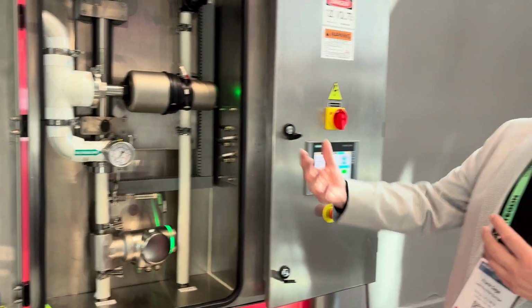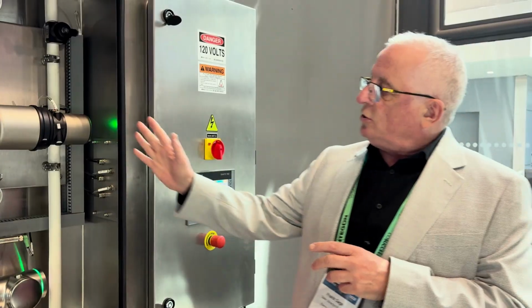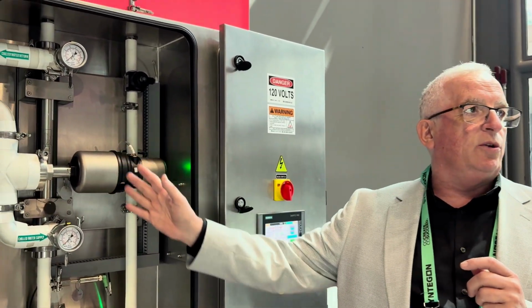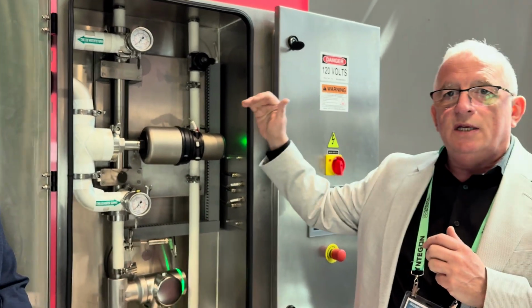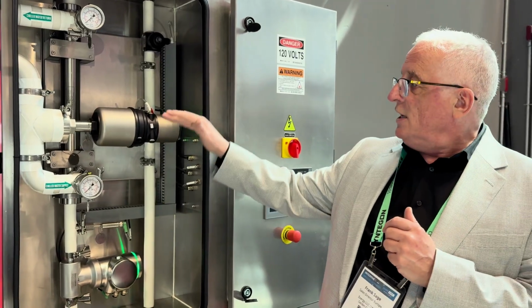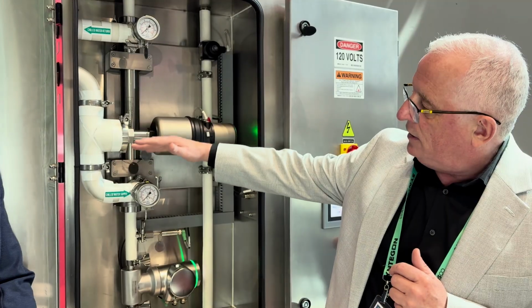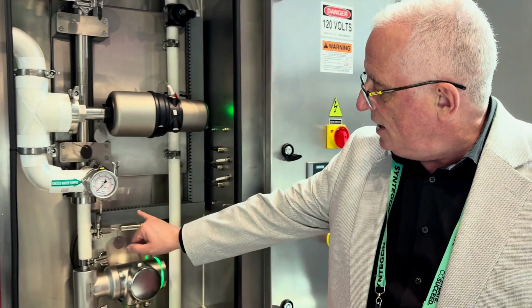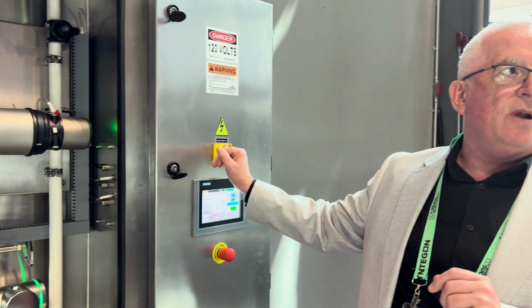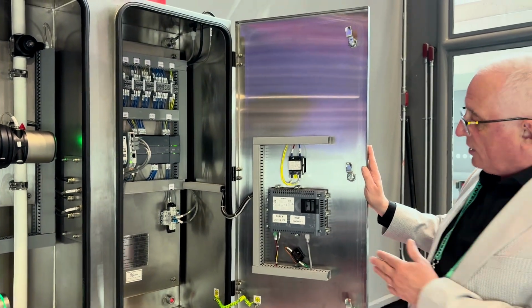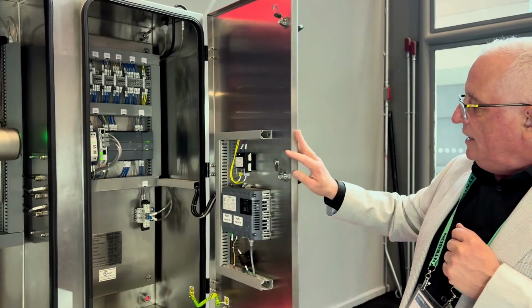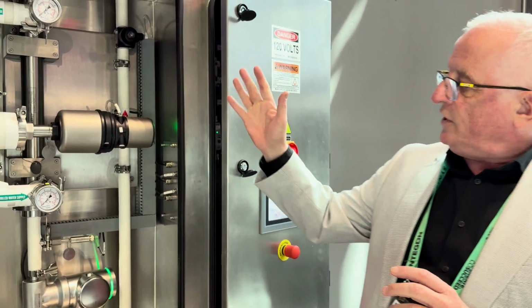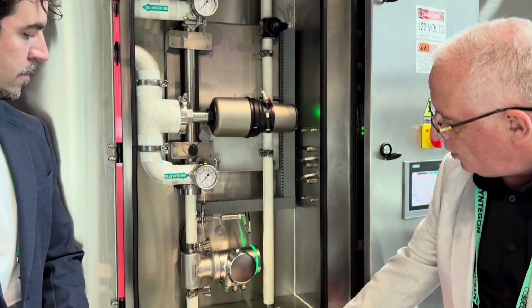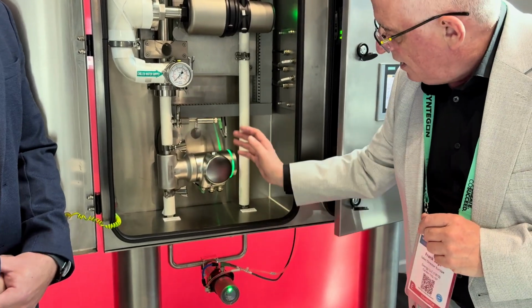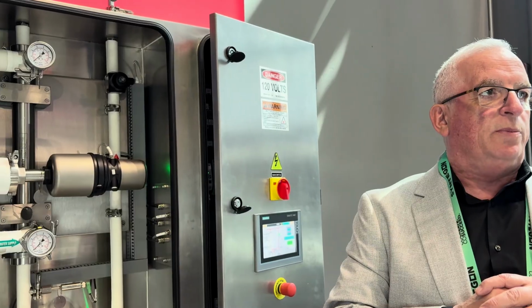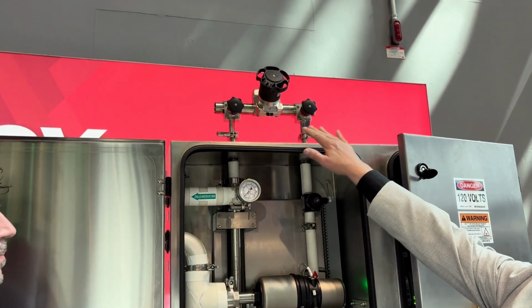So, for example, if this unit was to deliver different flow and temperature, to control the temperature, we use the Burkert PID control valve on chilled water. So if the customer says, okay, I want 60 degrees, I want 40 degrees, I want 20 degrees, this will open the chilled water supply until that temperature is reached. You have a temperature probe here. We'll go back to the pre-programmed PLC here. We're showing a Siemens. We use Allen Bradley in the USA, but that will all be set up in partnership with the customer. This will get us temperature. When the temperature is right, the valve will open. The flow meter will also measure the flow, and then if there's a different flow to the 5 GPM, the valve would open then.